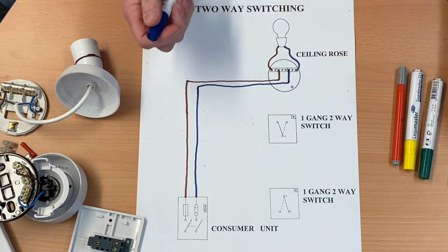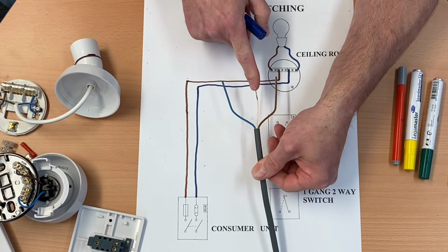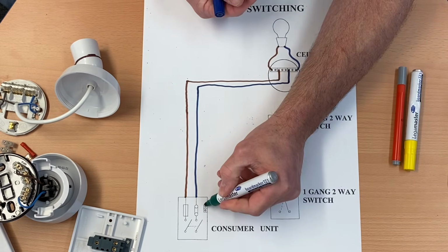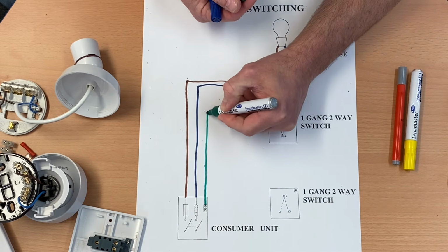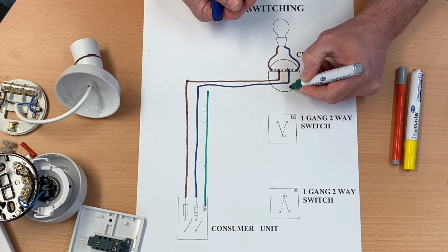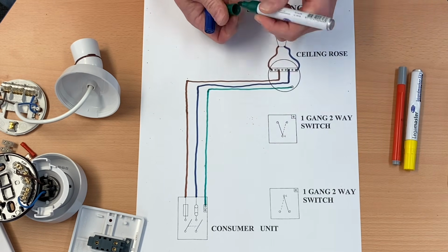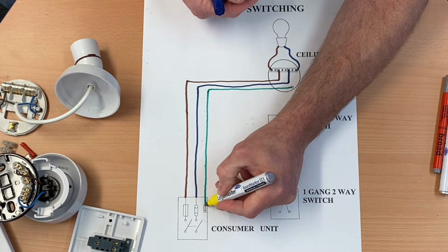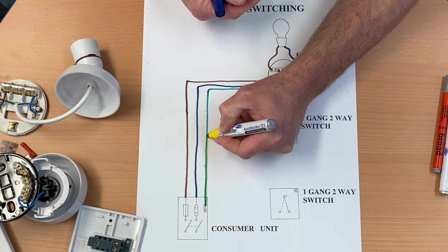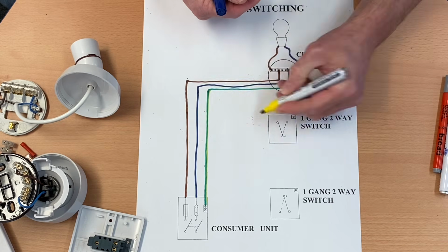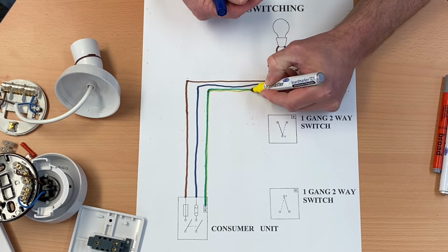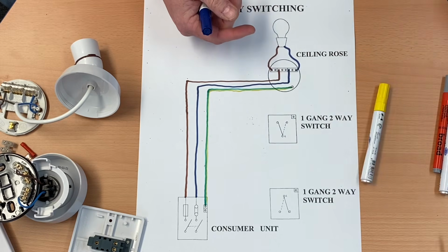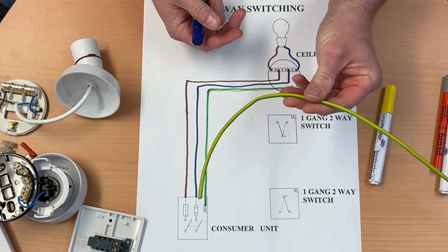And we're now going to bring in the final connection, which is our CPC. So from the consumer unit to here. We talked about in a previous video, didn't we, that the CPC isn't really required for these type of light fittings because they are fully insulated. They're all plastic, but we know light fittings can easily be changed for metal ones, making them exposed conductive parts. Just putting a little striking line down the side there so it's actually green and yellow. It's only one cable, remember, that's not 2 cables, that's just trying to show the outer green and yellow sleeving.